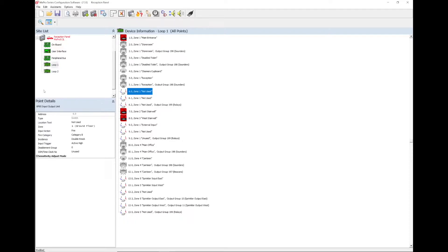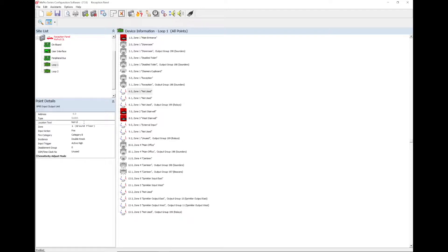When a device is highlighted on the right, the point details are displayed on the left hand side. The location text and the zone number can be changed so that it is more relevant. For example, the location text could be labelled as external input and the zone number can be changed so that it does not get linked to a fire zone.